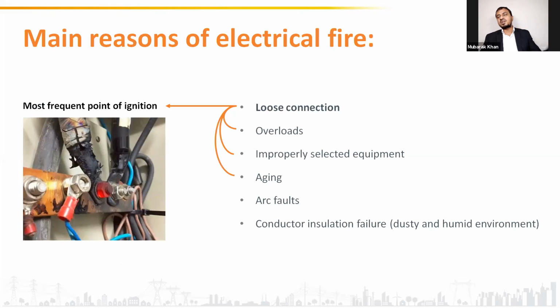Now, a little bit more about this slide. Under normal scenario, everything is okay. The system is running normally. But if there is an overload, the whole line is subject to a little bit of overheating. But which point will get overheated first and faster? That point is the point of a loose connection. If the connections are not proper, in case of overload, the loosely connected point will heat first and later on other areas will heat, right? So that is why, in case of overloads also, loose connections are the places where we experience failures.